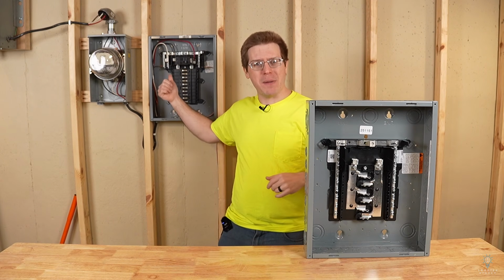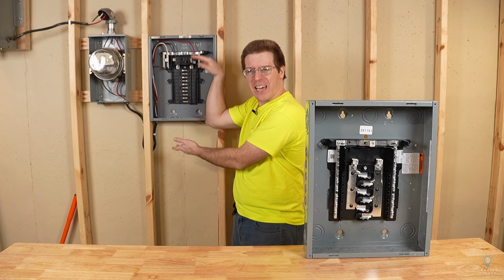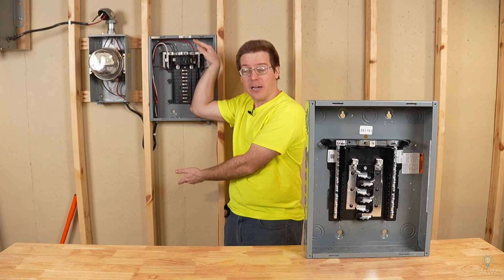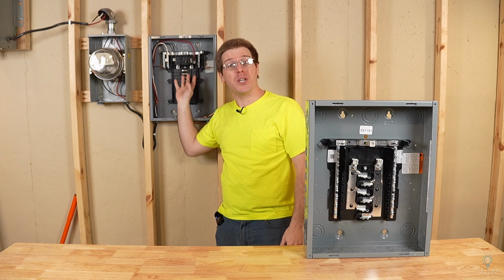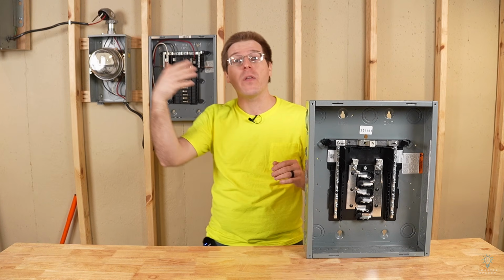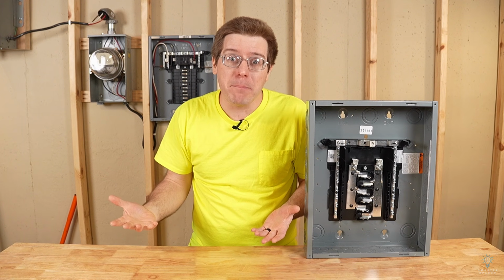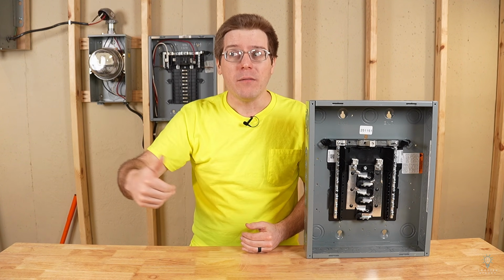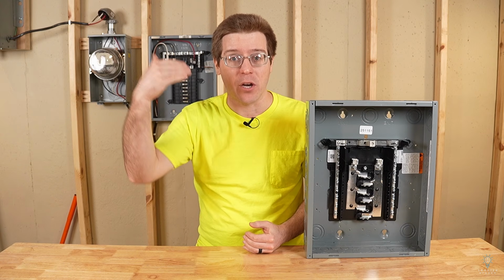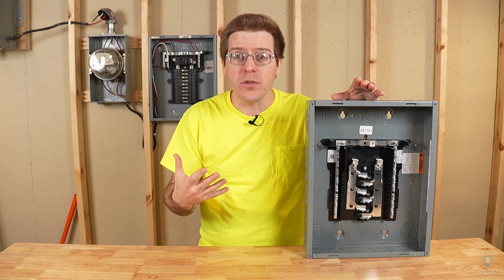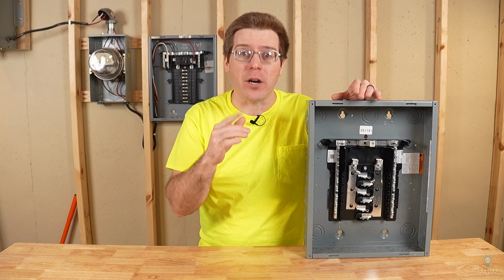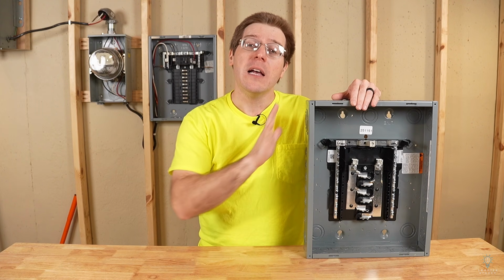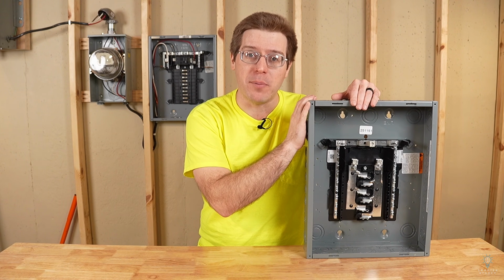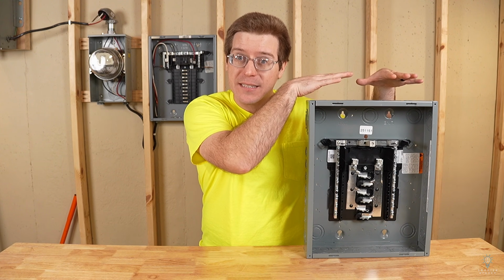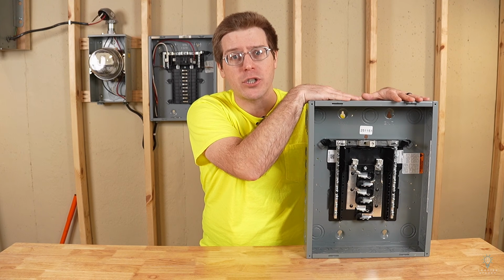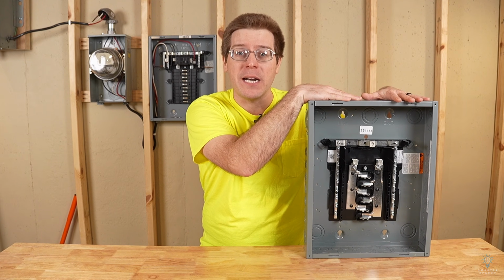Imagine, if you will, this main panel was larger, okay? So we had a lot more circuit capability in here. Imagine we needed to run 30 circuits out of this panel to the other end of a building. Now, if that building is 100 feet long, you've got 30 circuits that need to go 100 feet, right? So rather than doing that, you could run just one feeder that's that 100 feet long, set a subpanel in that part of the building, and now all of your circuits can go to that subpanel and be a lot shorter. So it saves a lot of money in the long run.